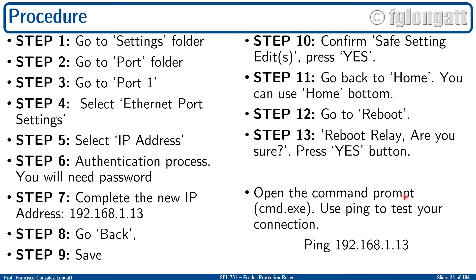The procedure is extremely simple — basically 13 steps. Go to Settings, then to Port, then inside Port 1, then go into Ethernet port settings, select IP address, put the password and fulfill the authentication process. Then go and change the IP address — in this case today I will use 192.168.1.13 because that is one of the IPs available at the lab. Then go back, save the settings, confirm the settings, and then go home to the home menu of this relay, because I would like to reboot the relay. After reboot I will use the command prompt tool in Windows to test the connection.